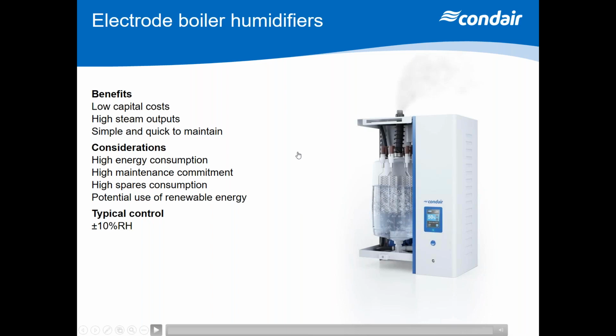So they were back to square one. So the moral of the tale is that before you tick a box on an AHU spec saying I want an electrode boiler, just a standard humidifier, look at what options are available. Will it give you the controllability that you want? And is it suitable for the water that you have?